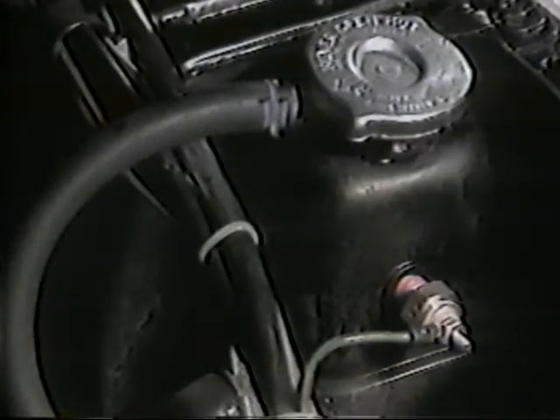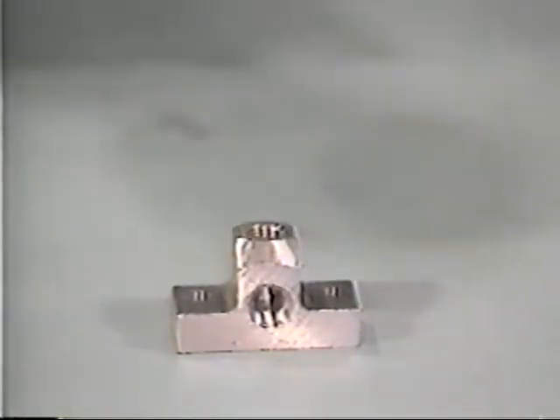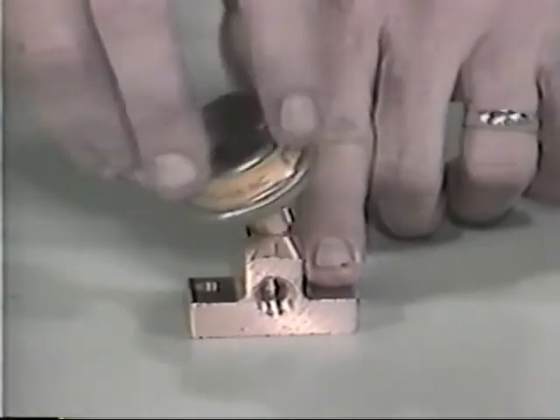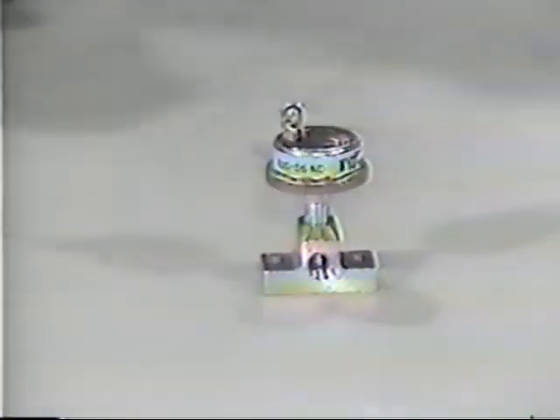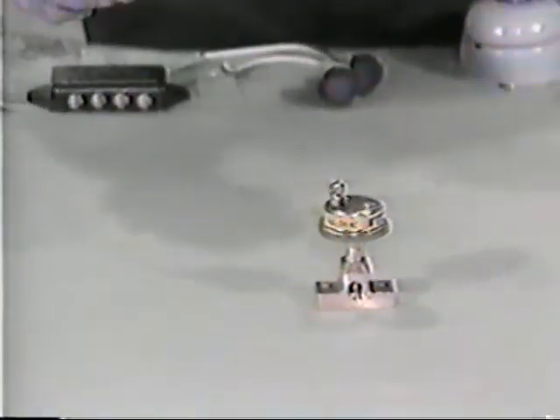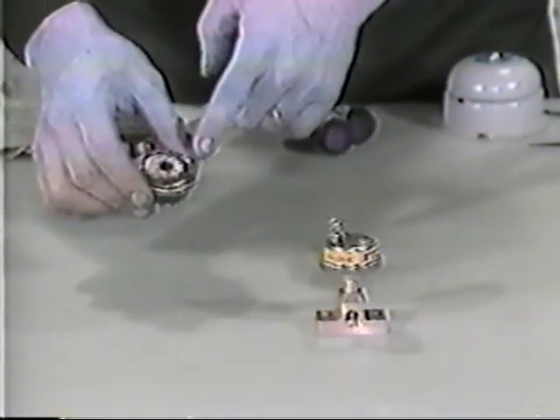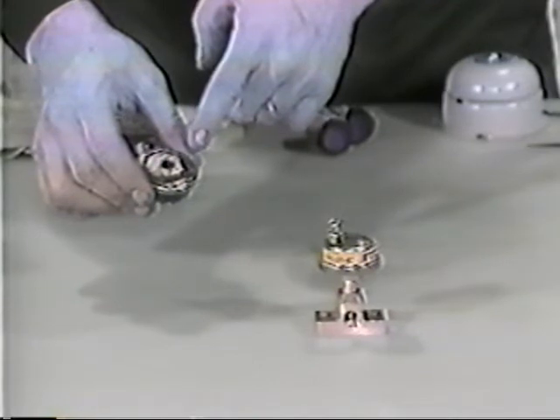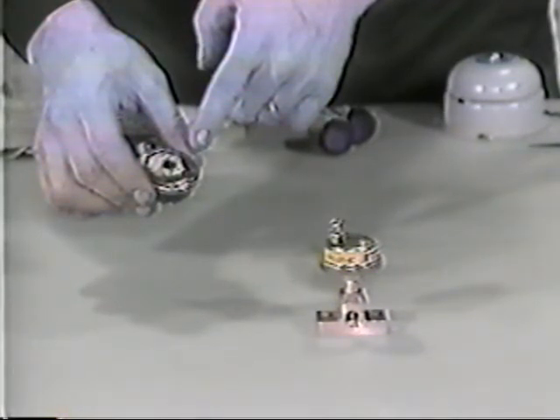The second troubleshooting area concerns coolant level probe location. With alarm-only systems, a bad probe location could cause false alarms. With alarm and shutdown systems, you can get false shutdowns as well. Third troubleshooting area, the need to locate the pressure stat at some place that is not on the engine. In alarm-only systems, a pressure stat mounted on the engine could cause oil leaks, false alarms, and short pressure stat service life. In alarm and shutdown systems, you also get false shutdowns.